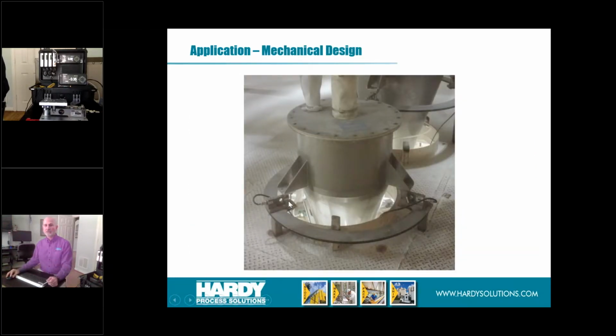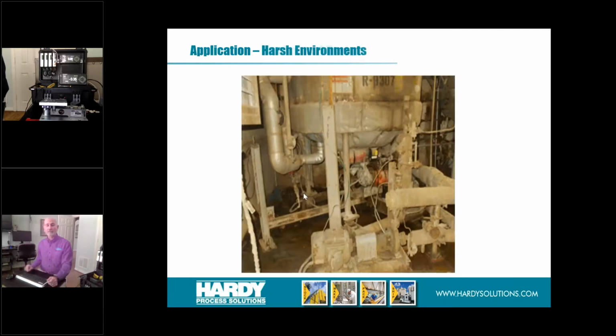These load cells are mounted here. The problem is there's no support under this point where the weight is coming out. Your support is out here and here, but it needs to be in a direct line with the force. This would be similar to your bathroom scale: take it off the tile floor, put it on a rug, and climb on it. You're going to get an erroneous reading. So that needs to be considered.